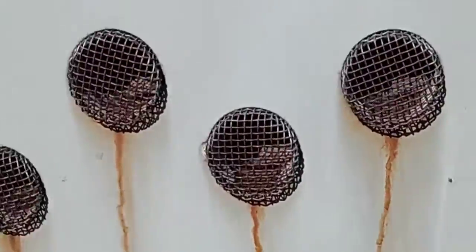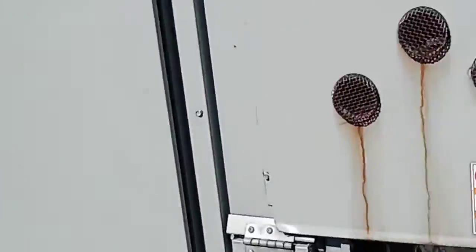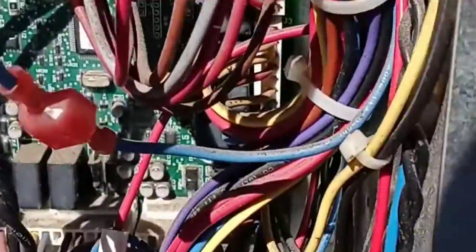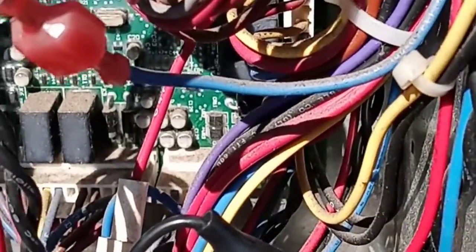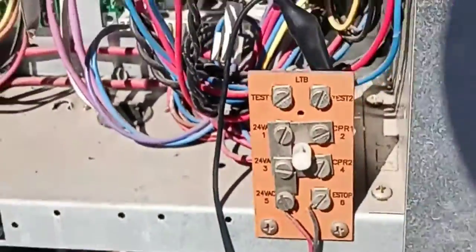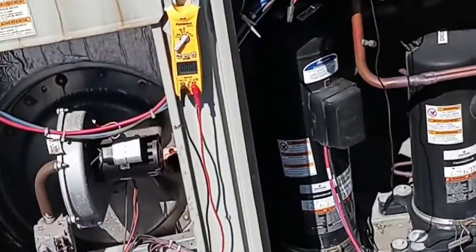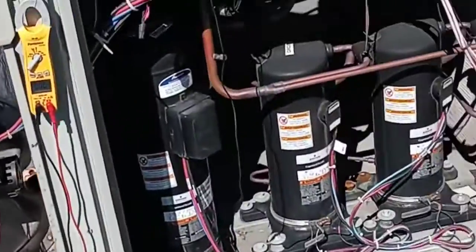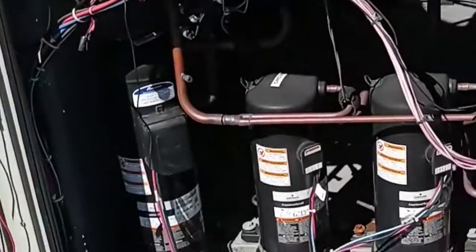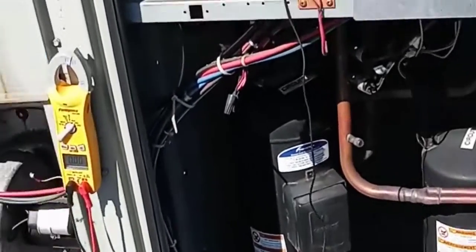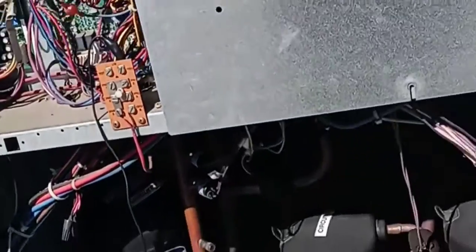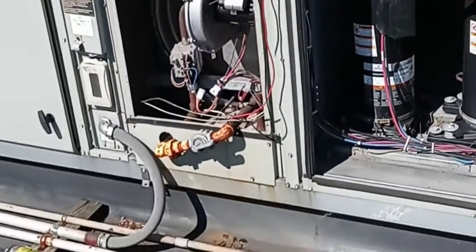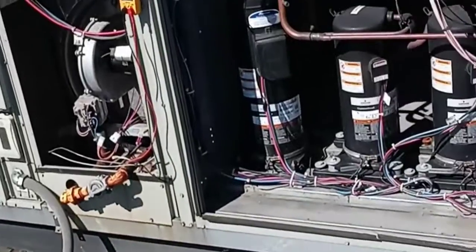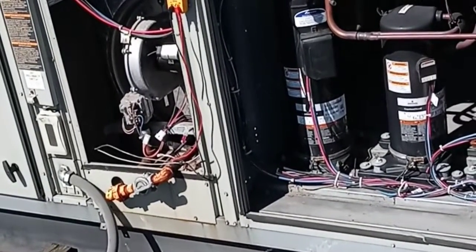I turned my unit back on because I had turned it off for a minute so I could check the belt. Turned it back on, and as you know, these units have the famous test mode you can run them in. If you jump out these two tests, if you short these out right here, you'll cycle through all the modes of these units. So you'll put your jumper on, fan will come on. If you leave the jumper on, it'll cycle through all the test modes by itself. Leave the jumper on there. I think it spends about 4 or 5 minutes on each mode.